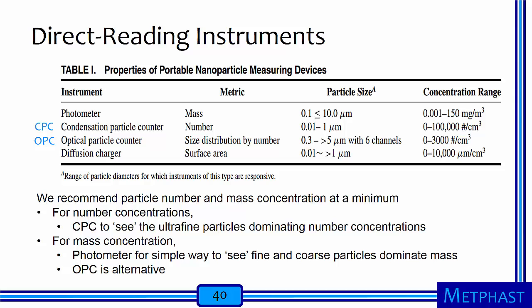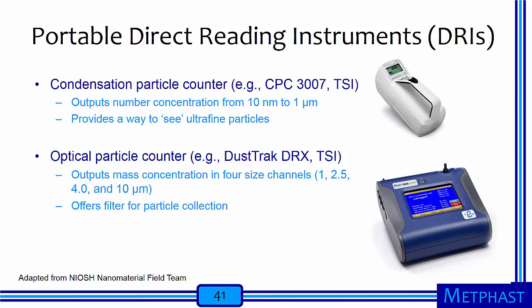Alternatively, an optical particle counter can be used to assess number concentration by size of particles larger than 300 nanometers. If used, make sure the optical particle counter you select provides output in mass concentrations as well as raw number concentrations. This slide shows specific direct reading instruments used by the NIOSH nanomaterial field team, including a condensation particle counter to measure sub-micrometer particle number concentrations, and an optical particle counter that can measure larger particles — in this case mass concentration in four size ranges: 1 micrometer, 2.5 micrometer, 4.0 micrometers, and 10 micrometers. This device also offers an after filter so that the optical information can be back-corrected to a real measure of particle mass concentration.